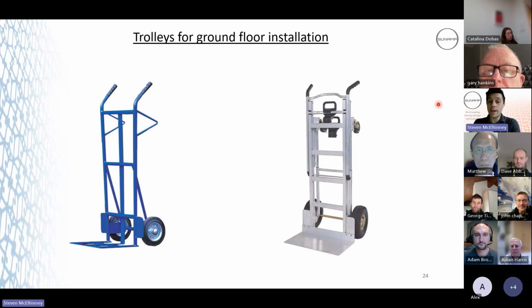So what we would advise is using proper trolleys. For a ground floor installation, you can use a heavy duty trolley. You would just get a sack barrow trolley that can cope with the weight. You'd have to look at the manufacturer's instructions for the specification. That's obviously a bit heavier duty. Then you get your ratchet straps and strap the battery to the trolley itself, so it's not going to slide off the base plate here.